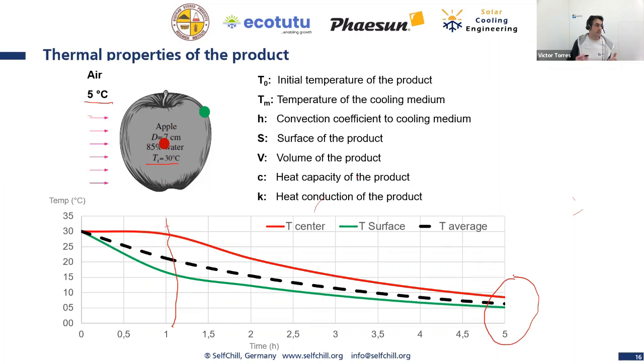Okay, so it is not like this that we are putting a product in the cold room and then it is cold. Imagine when you also have several crates at the same time, then you have to make sure the ventilation, the circulation of air is given so that the products can cool down fast. This is important if you are putting, for example, a lot of tomato crates inside the cold room at the beginning without taking care of ventilation and air circulation, then probably it will take more than 24 hours to achieve the temperature you want to achieve.